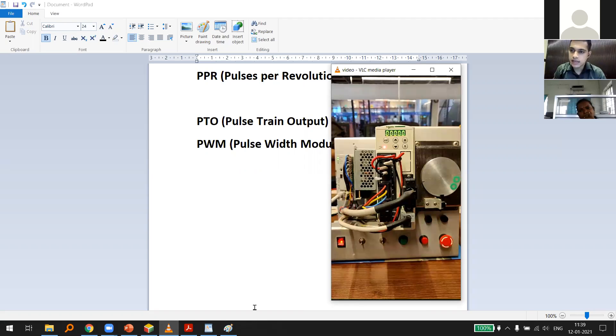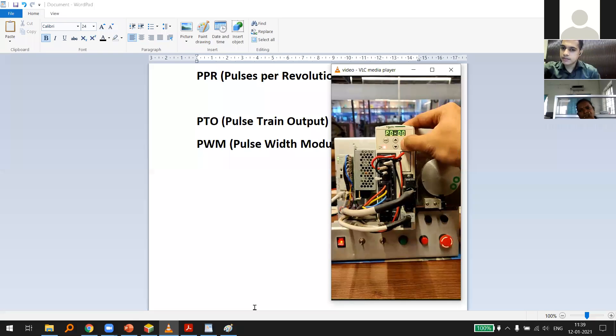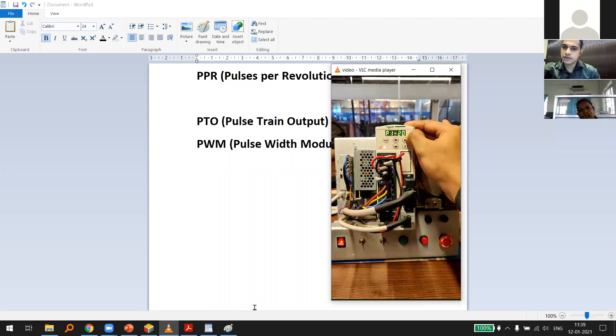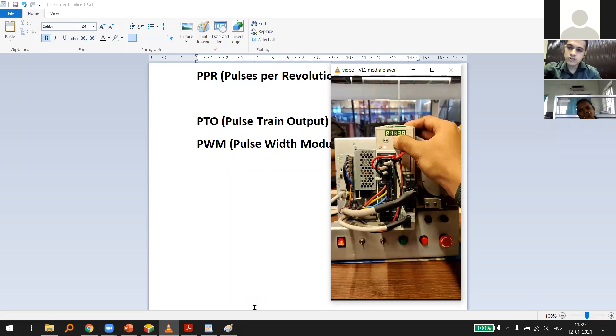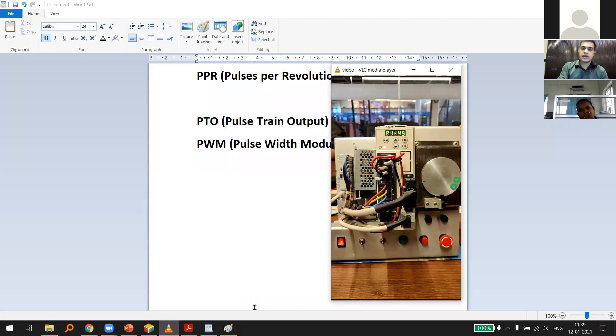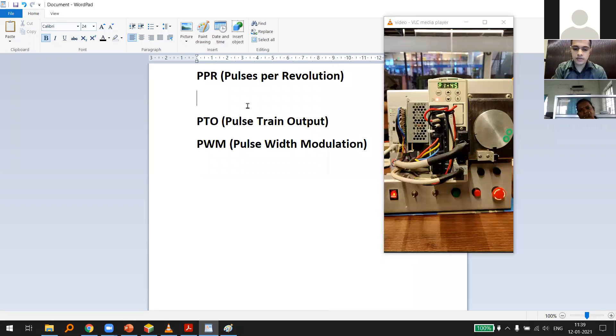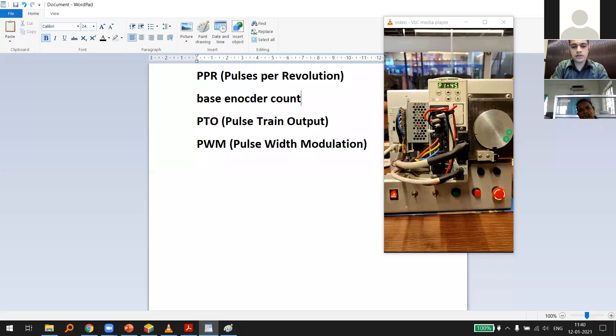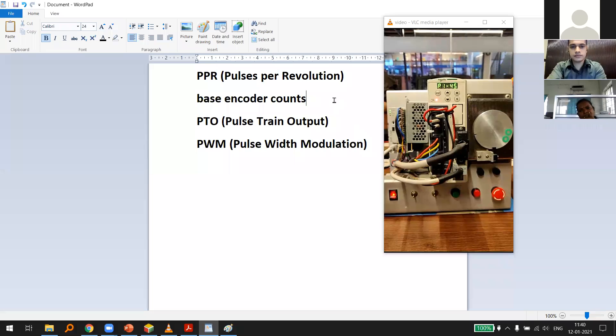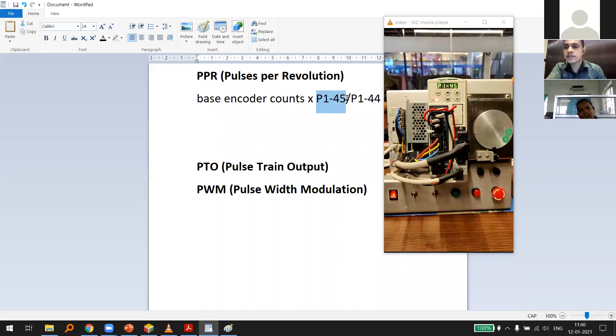PPR is set from the servo drive. For Schneider Electric and many other servos, they use a numerator/denominator type thing with specific parameters. For example, parameter P144 shows a value of 640, and P145 shows a value of 1. The formula is: PPR = Base Encoder Counts × P145 ÷ P144.